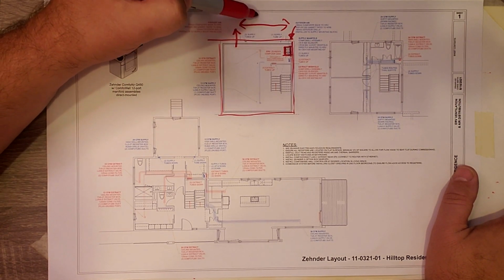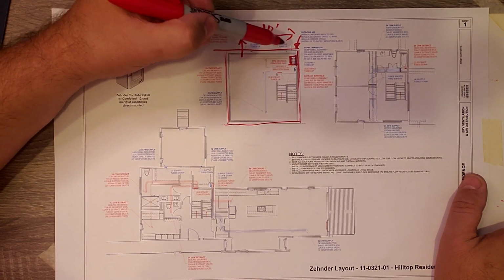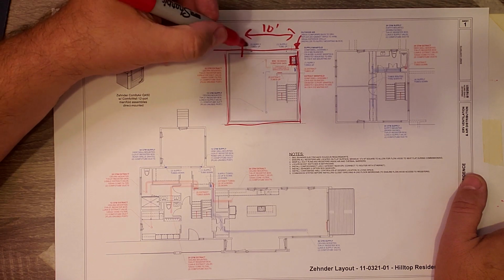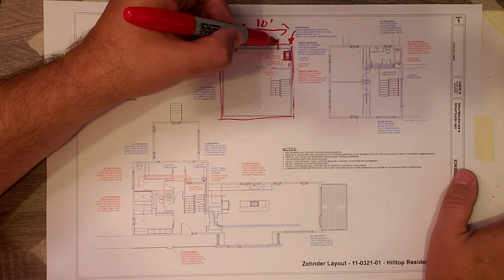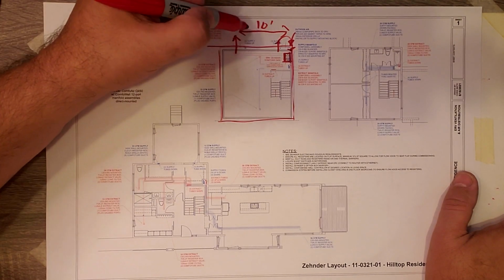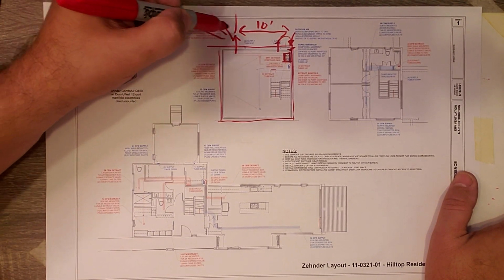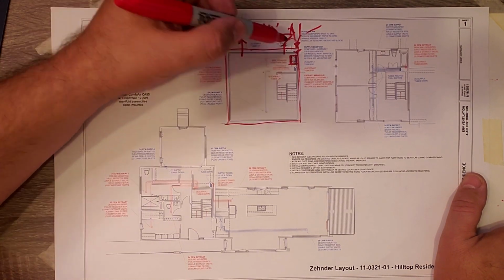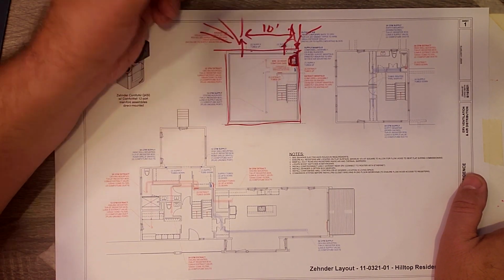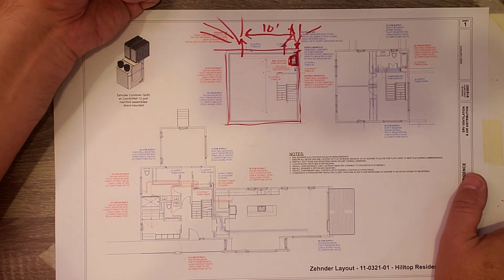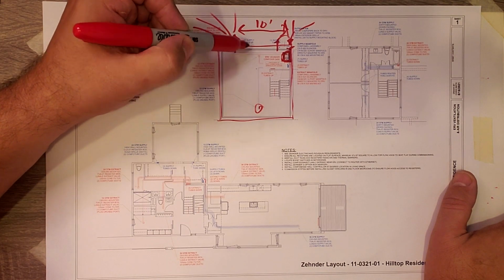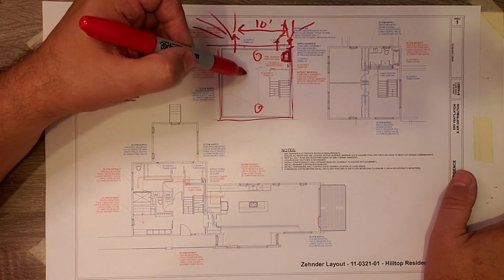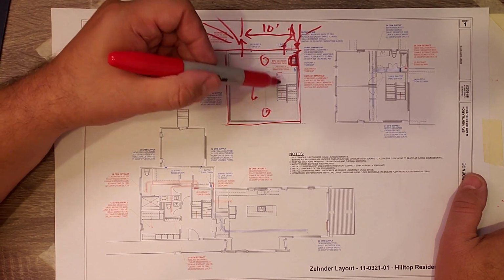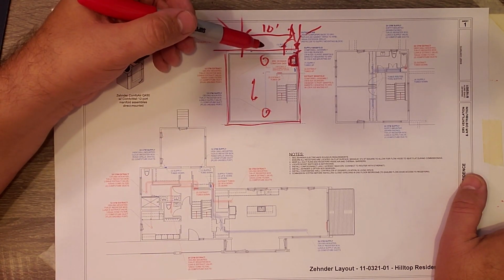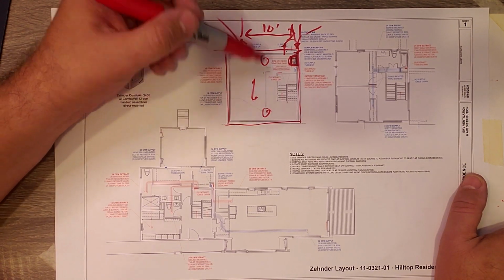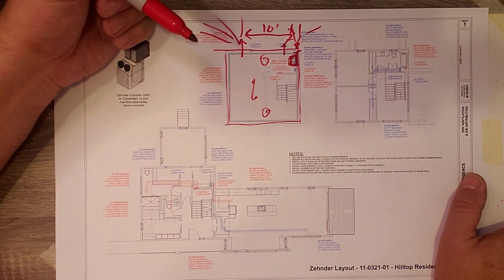Because we don't want any re-entrainment - we don't want to be throwing bad stuff out here and have it come right back in. So we want to get that 10 feet away, so bad stuff goes out and good stuff comes in here, and then it goes into the system. You can see here in the basement we actually do have a supply and one exhaust, so that's kind of balancing out the basement. We put just a little bit of CFM in there, talking 12 CFM, but it's just enough to move the air around.